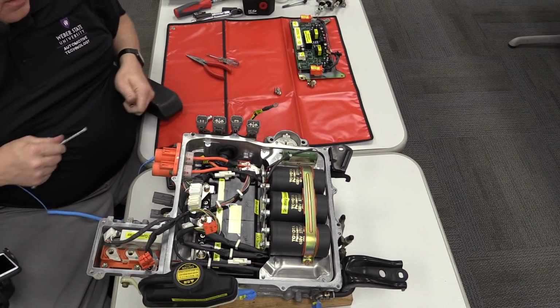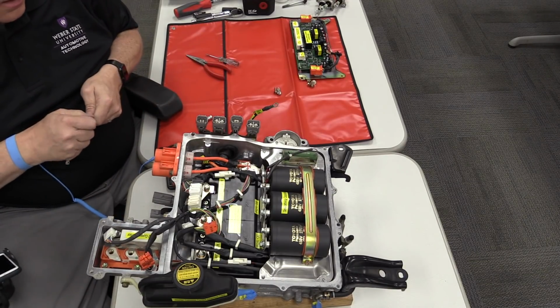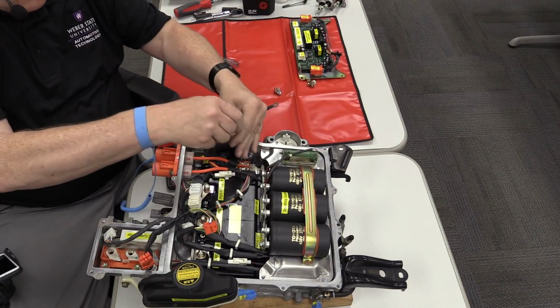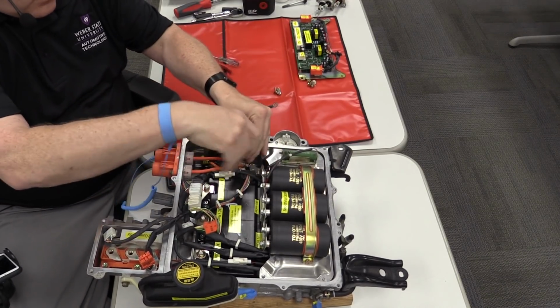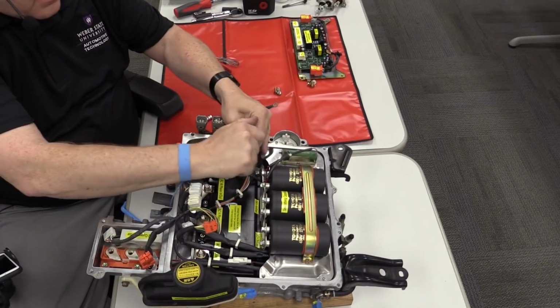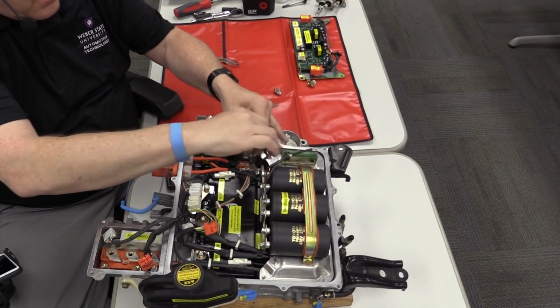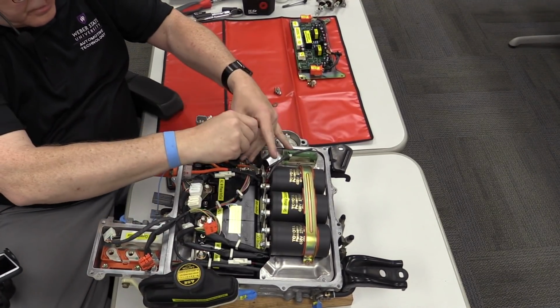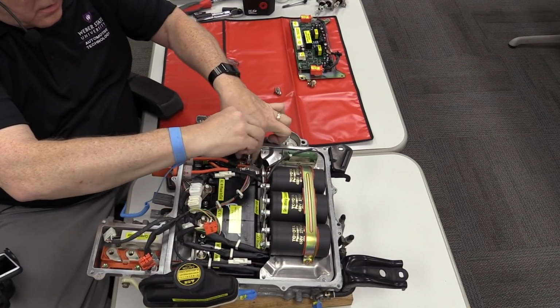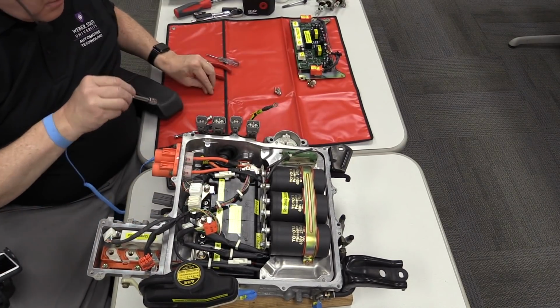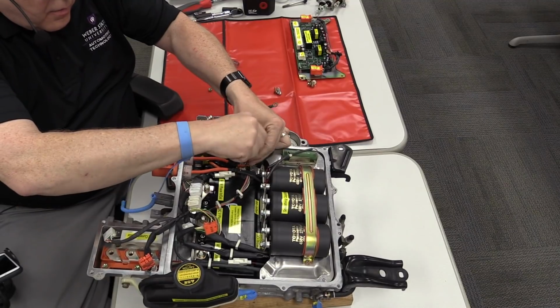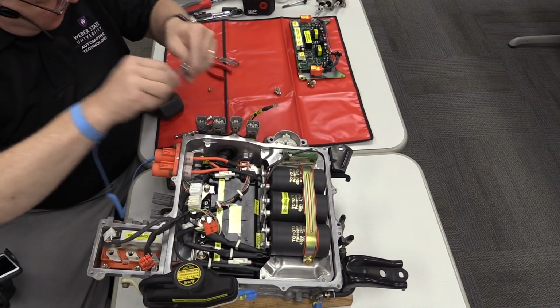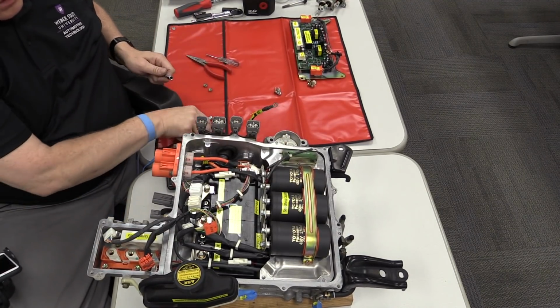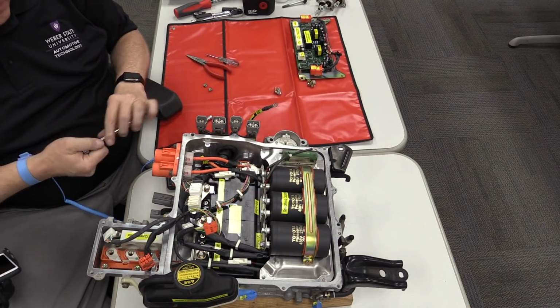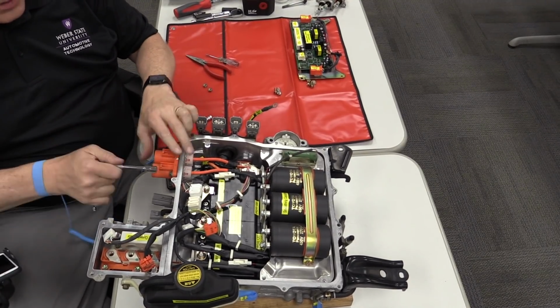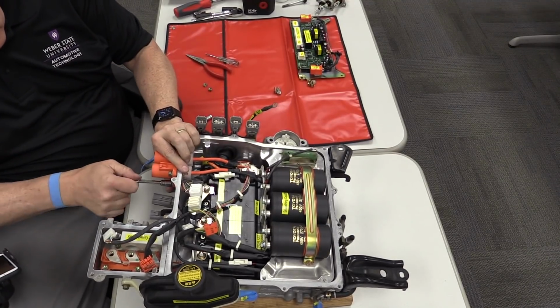So we've got to disconnect not only the high voltage electrical connection from the battery, but also the capacitors from that. There's a nut for the negative cable, a nut for the positive cable, and 4 bolts that hold this electrical connection to the case.